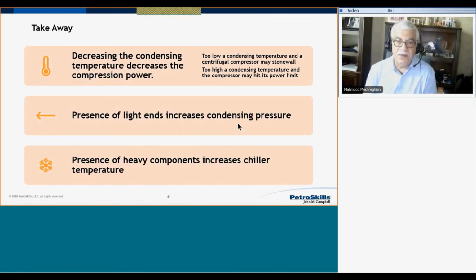The second item, presence of light ends increases condensing pressure. And if condensing pressure increases, that means compressor power goes up. And finally, presence of heavy component increases chiller temperature, and then you have to decrease your chiller pressure, and decreasing chiller pressure means more power requirement.